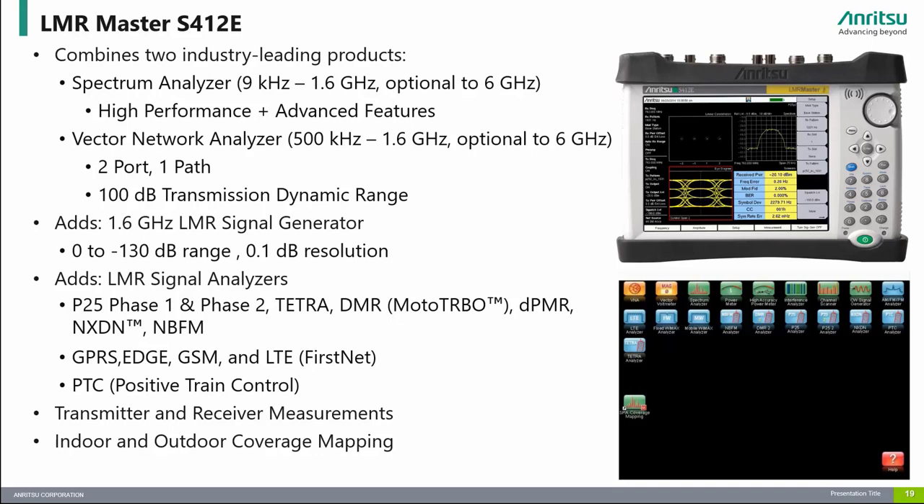The LMR Master is one of our most popular instruments as it combines a high-performance spectrum analyzer, vector network analyzer, and a signal generator with built-in LMR patterns. This instrument is ideal for customers engaged in testing the RF performance of land mobile radio communication systems such as narrowband FM, P25, P25 Phase 2, TETRA, and DMR. It also offers positive train control and GSM-R measurement options for railway operators, and options for testing 2G, 3G, and 4G commercial wireless systems. The LMR Master is Anritsu's Swiss Army knife, combining multiple instruments into a small, lightweight, and rugged package.